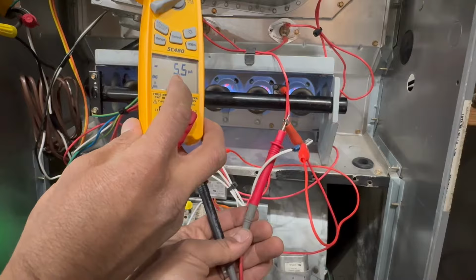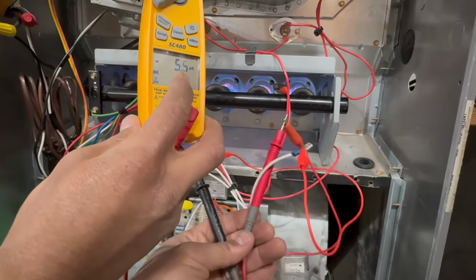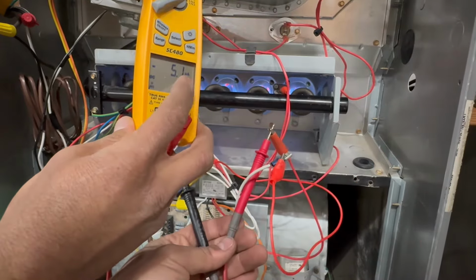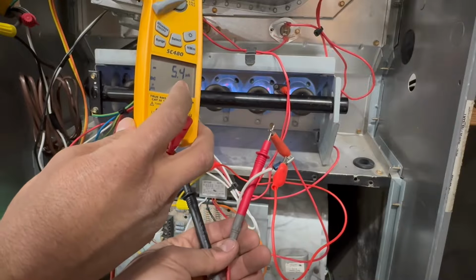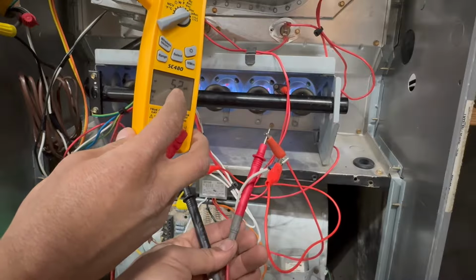But you see, I am reading 5. So if you go to a job and it says like 1 or 2, you might want to start thinking about cleaning that flame sensor. If you clean it and it still doesn't work, you might start thinking about replacing the flame sensor.